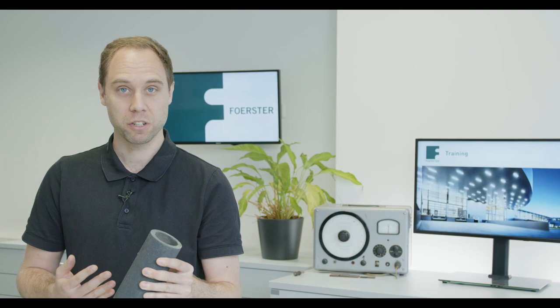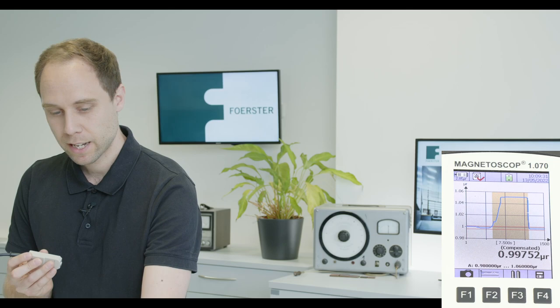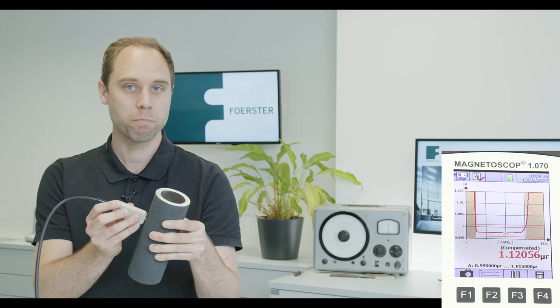So we have this tube with low high temperature corrosion, so a low permeability value. And we have this tube with a higher value of high temperature corrosion with a higher permeability value.